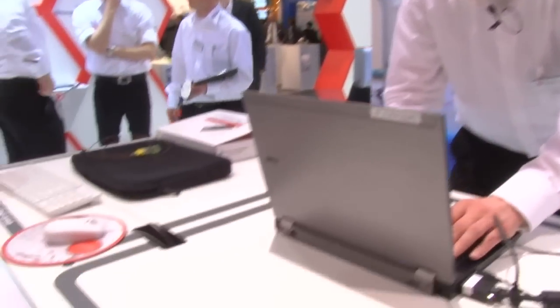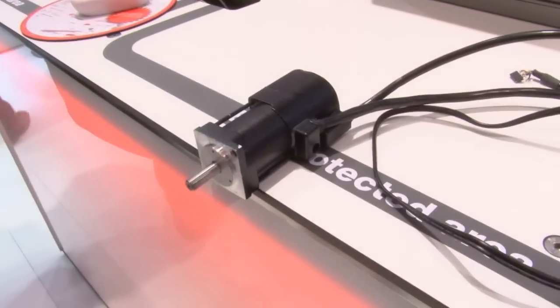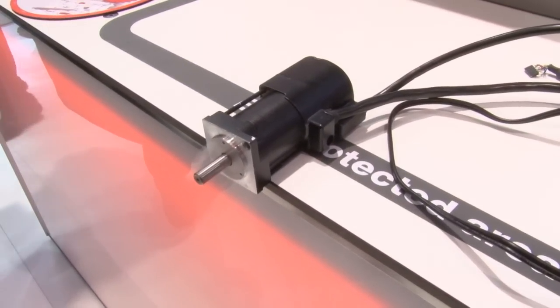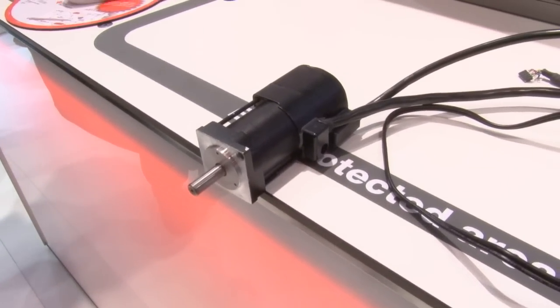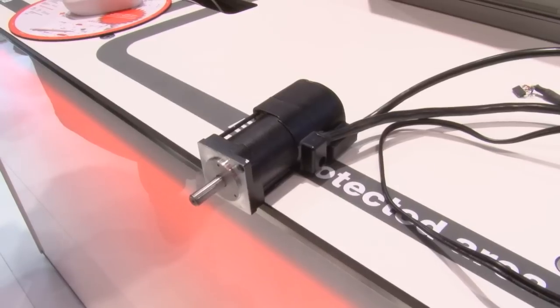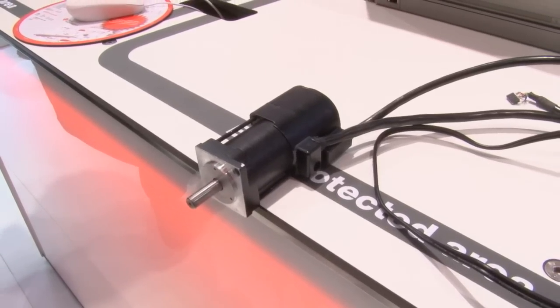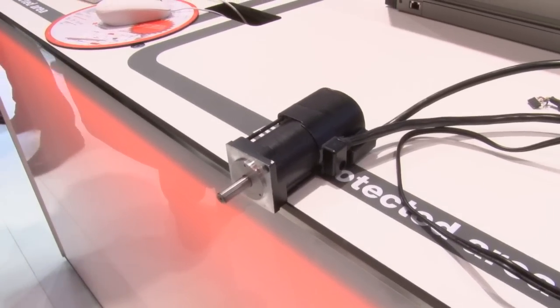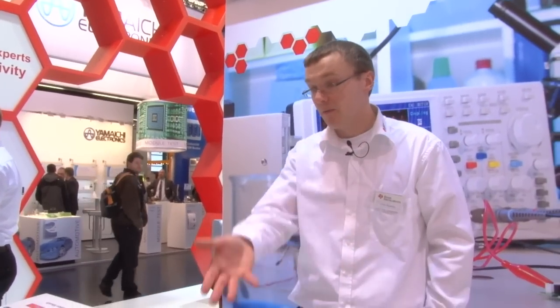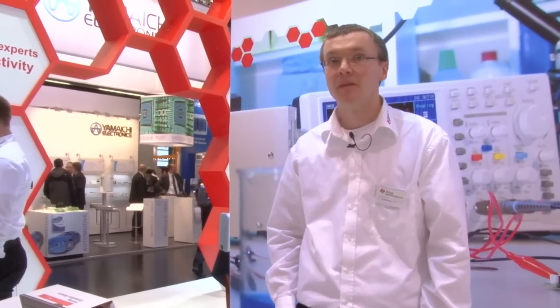Then I do the step response again and then when I press refresh you see that suddenly you have no overshoot when you run the motor and this you can really do with the motor running and you don't have to simulate it. You can actually test your proper hardware and see how it runs and all of it done with the running system. And this is part of what we can offer with Instaspin FOC and again this is all sensorlessly done.